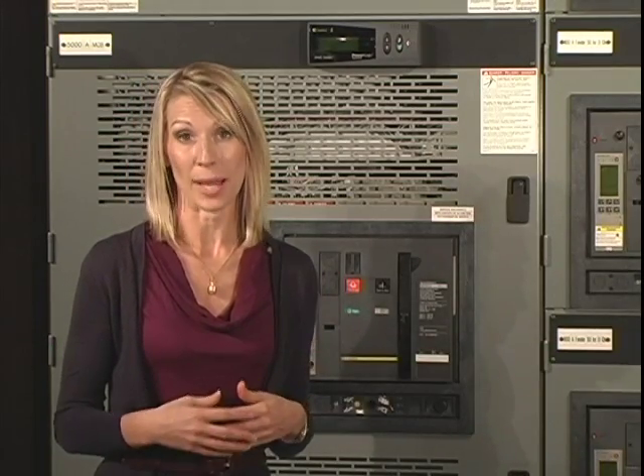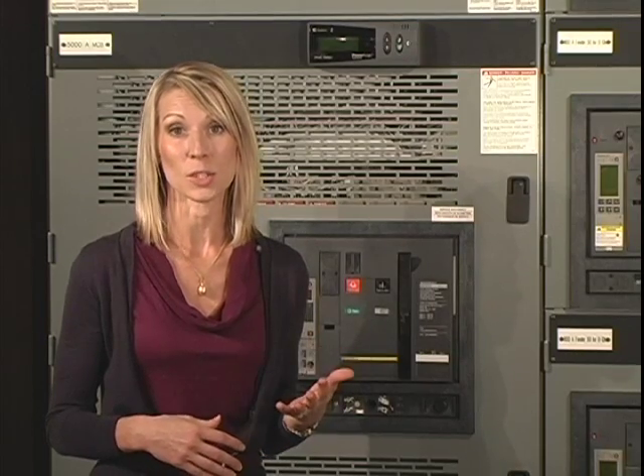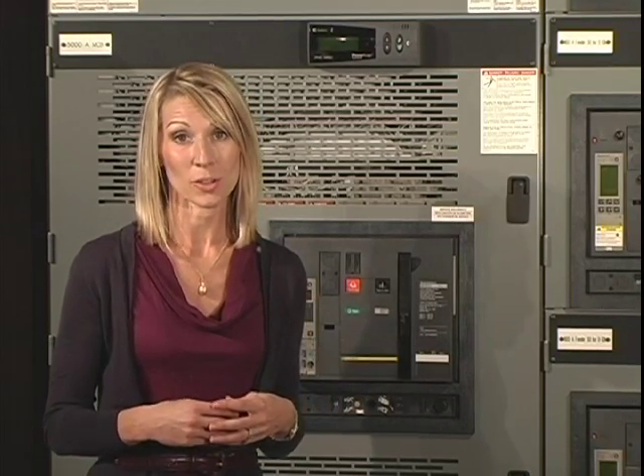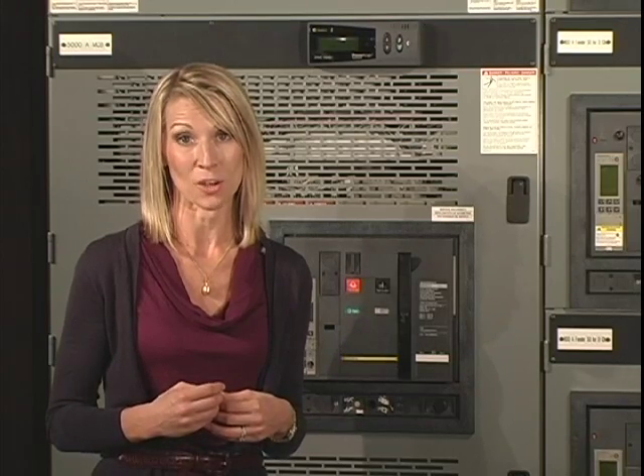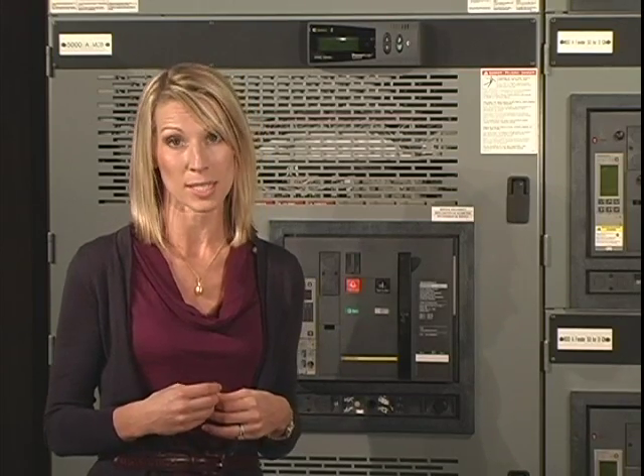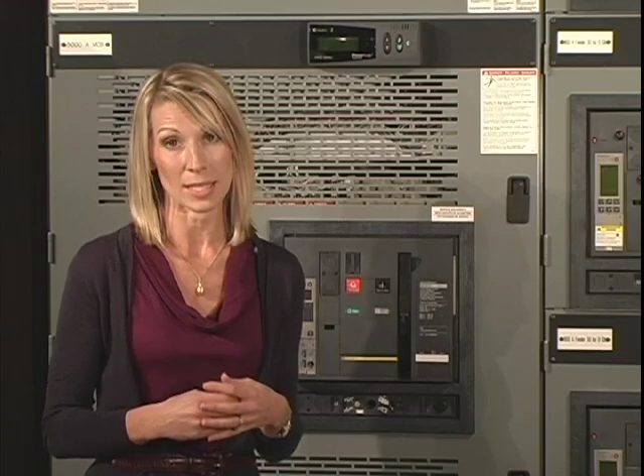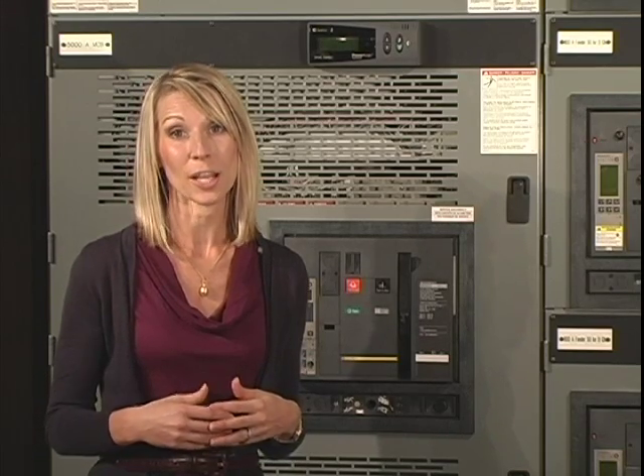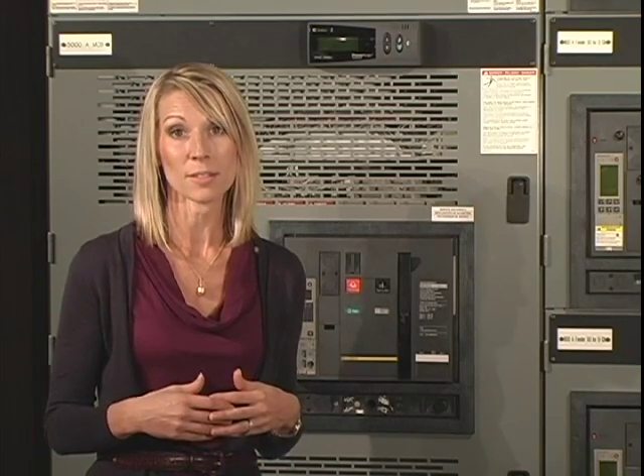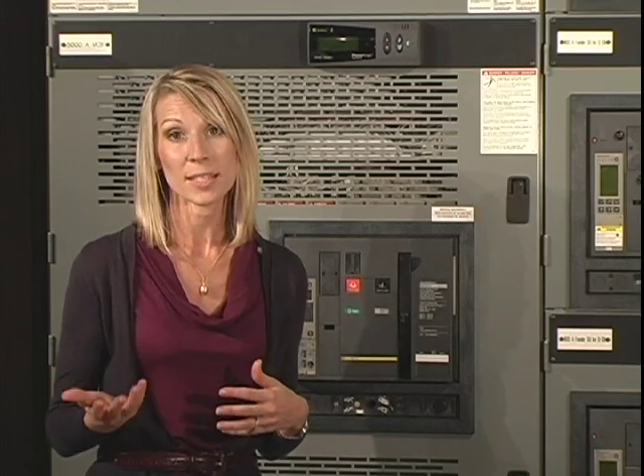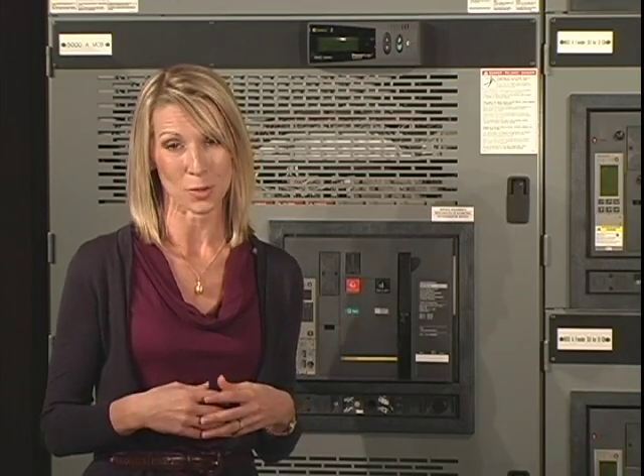Each facility manager has to evaluate the operation relative to reliability factors and operating costs. This version of the Masterpact breaker was placed into obsolescence in 2004. The Schneider Electric commitment for breaker support of 10 years is scheduled to end in 2014, and parts availability is being depleted. Therefore, Schneider Electric has engineered and developed a cost-effective means to upgrade the existing switchgear with the new version of the Masterpact breaker.